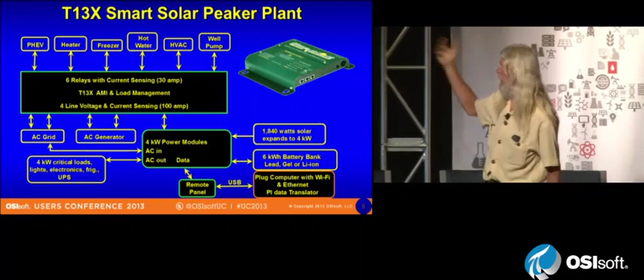The typical U.S. house has an average load of 1.7 kilowatts, but it has 100 amp service, which is 24 kilowatts. There's a really big difference in those two numbers. They only need the 24 kilowatts because statistically, every once in a while, all those things could come on at the same time. But if you have intelligence, you can force them to take turns.